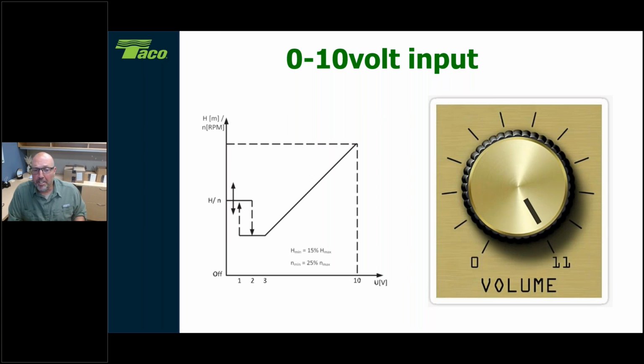All right, so your 0 to 10 here is now, and if you're not familiar with 0 to 10, it means we're going to send a signal across a pair of wires. If the signal is 10 volts across that wire, that means make the pump run at 100% speed. If there are 5 volts across the wire, run at 50% speed. And we have a couple of different ways that we're going to accept that 0 to 10 input, based upon the equipment that might be sending us that signal.